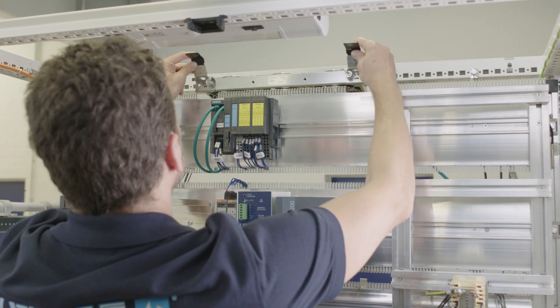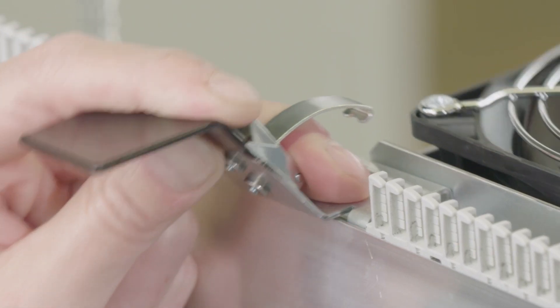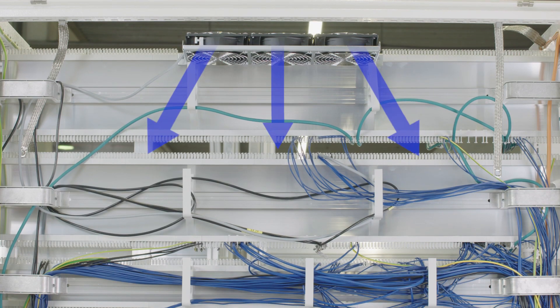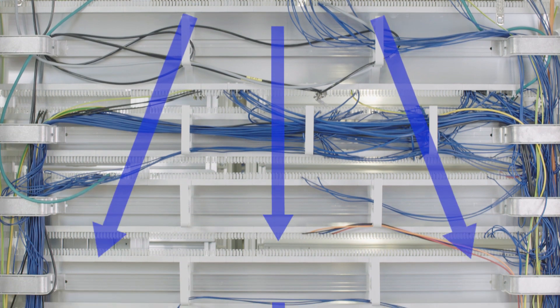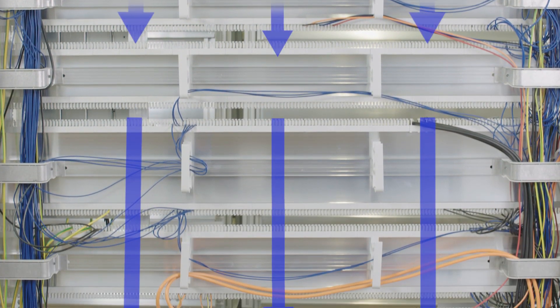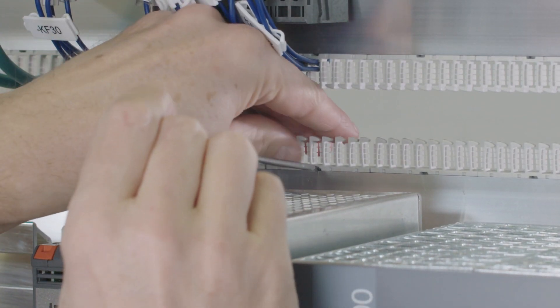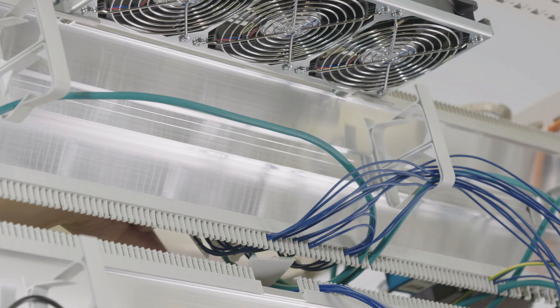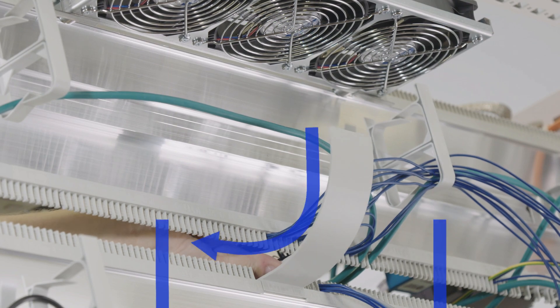An important accessory is the air blower fan to create a stable cabinet climate. The air blower is controlled by a control unit and switches on automatically as required. There are air blades for targeted cooling ventilation on components with particularly high heat loss. The blades are installed instead of the comb segments. The use of air blades avoids dangerous hotspots.